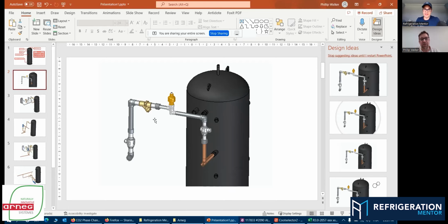And we even go a step further. So don't forget, this is all our high side right here. We could have 1,200 pounds. She's flashing down to the low side here. So this is why you see some K65. In our new design with our flash tank manufacturer, this is now all stainless coming in. In terms of manufacturing, it's easier for us to put a socket weld here and come out completely in stainless. So just to say, if you're working on one of our systems, this whole line here is stainless, which doesn't mean it's all high pressure. This is really the high pressure side. We're flashing down. This is the side that we're at, say, 525 PSIA, 32 degrees Fahrenheit coming in here.